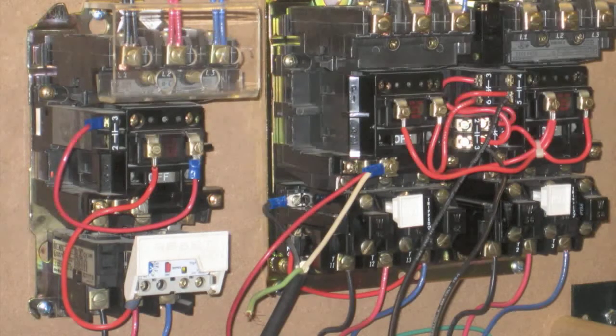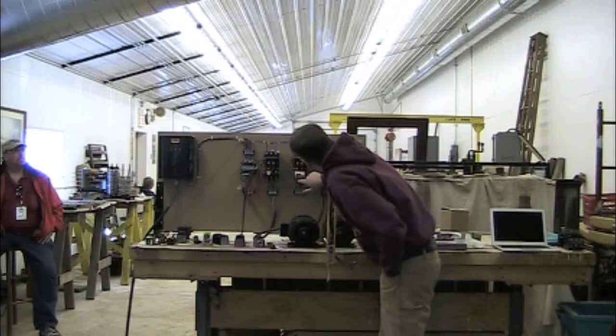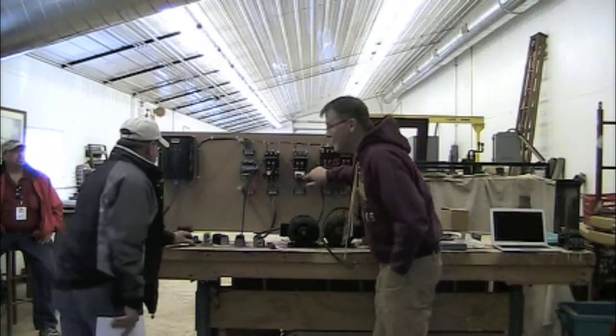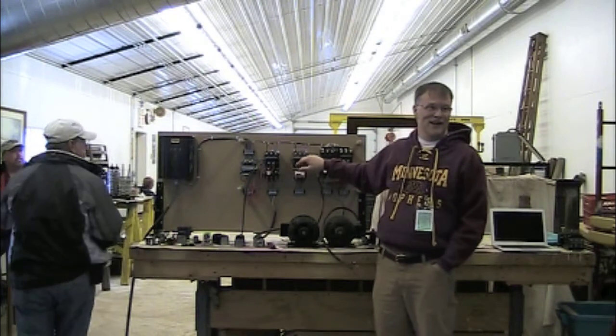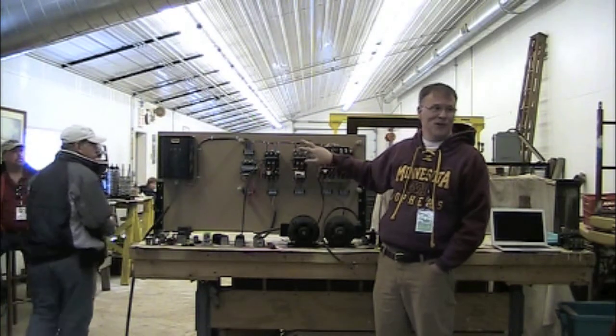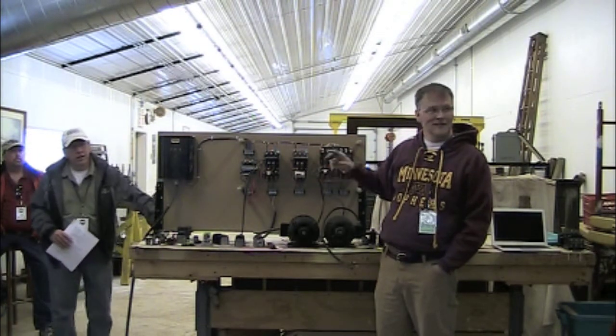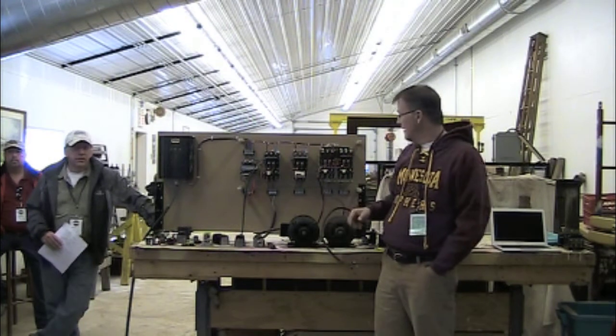It's just got a dial on it. And like I said, in the NEMA world, it's very consistent in the terminal numbering. It's all made to be easy to hook up, not think much about it. You know, it's terminal 2, terminal 3. And this is actually marked with terminal 95, 96, 97, 98, which are standard IEC markings for the normally open and normally closed contacts on the overload block.